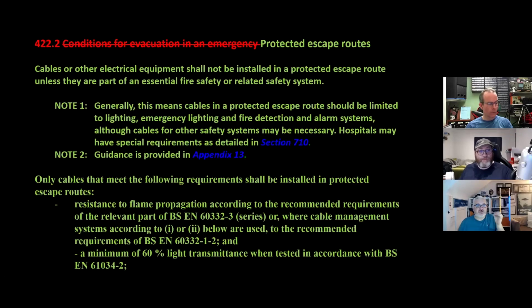Now there's notes. Note 1 - generally this means cables in a protected escape route should be limited to lighting, emergency lighting, fire detection and alarm systems. Although cables for other safety systems may be necessary - hospitals may have special requirements. Now, a fire engineering approach - if you couldn't find another route, you would look at maybe, if you had sub-main distribution, looking at that cabling being fire survival within an enclosed, compartmented area, or other methods and means.